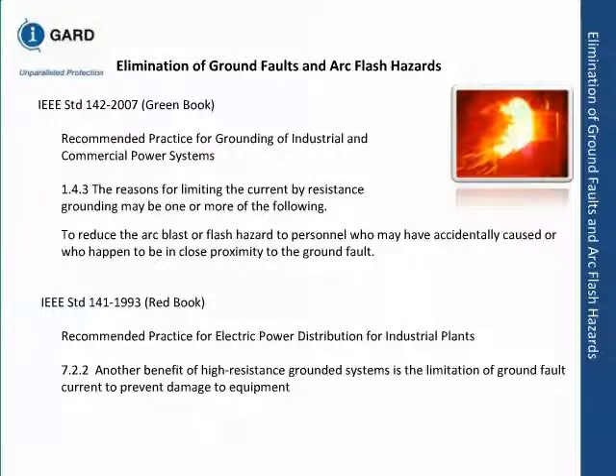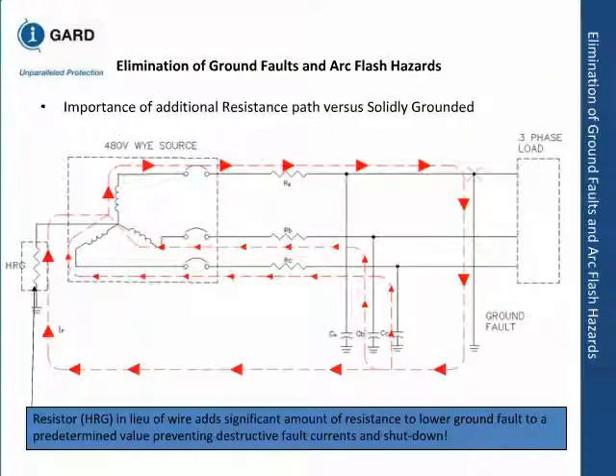This is just to show you the path. If you look at the red arrows, when you have a solid fault, and you write down Ohm's law, current is equal to voltage divided by impedance or resistance. Since this path has such low resistance, current will go almost to infinity. If we can introduce a high-resistance grounding system in there, current is limited. So that's the basic theory, which is very simple and credited with preventing a lot of arcing faults.